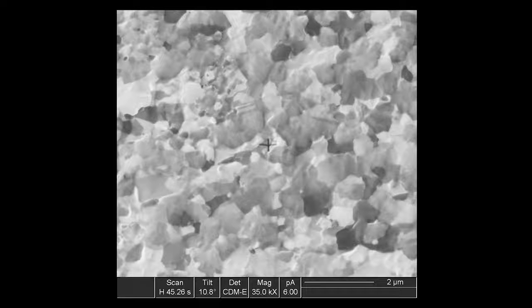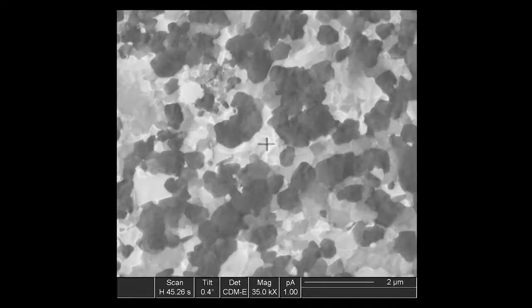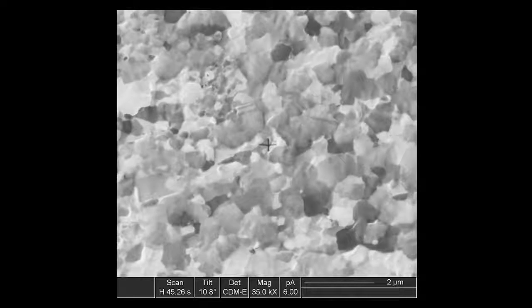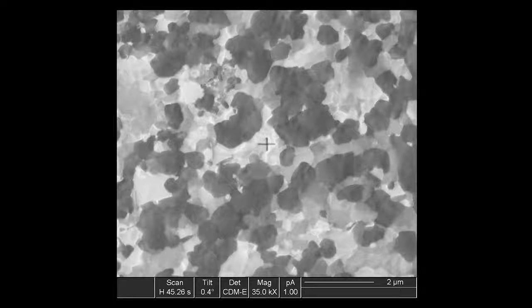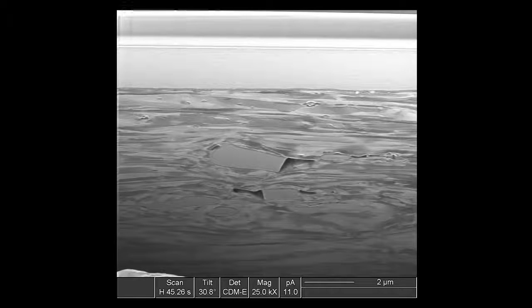So when we take this exact same field of view and tilt it just 10 degrees, the contrast on about half of the grains switches to a very dark color because the angle of the crystal planes in those grains has changed sufficiently that the ion beam doesn't provide the same contrast for those surfaces. And so if we toggle back and forth, you can see the outlines of the grains are all the same. It's just a matter of angle, and that's why we see the grain structure contrast.